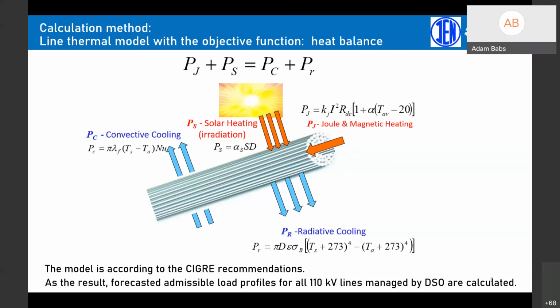In this equation, there are coefficients and constants typical for each wire span. For example, TS, the temperature of the surface of the wire, is the limiting factor, corresponding in a simple way to the sag of the wire in that span. This model follows the CIGRE recommendation, and using it for all spans in all lines, the admissible load profiles for the lines can be calculated.